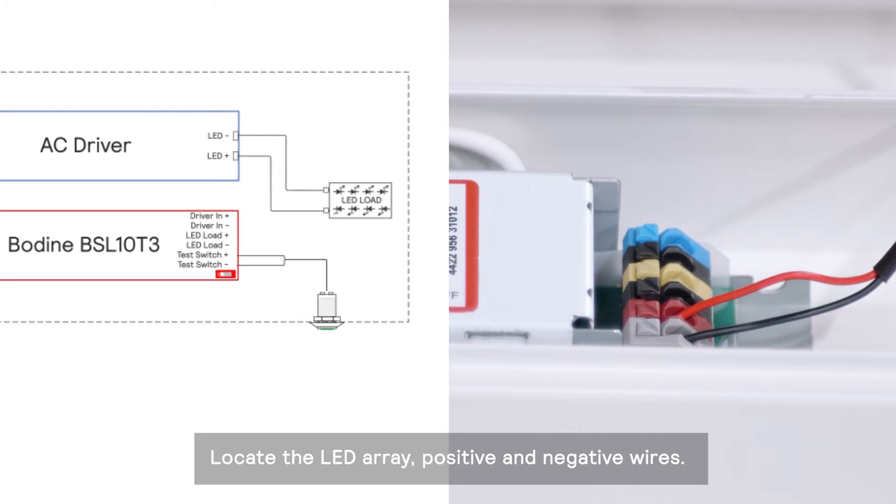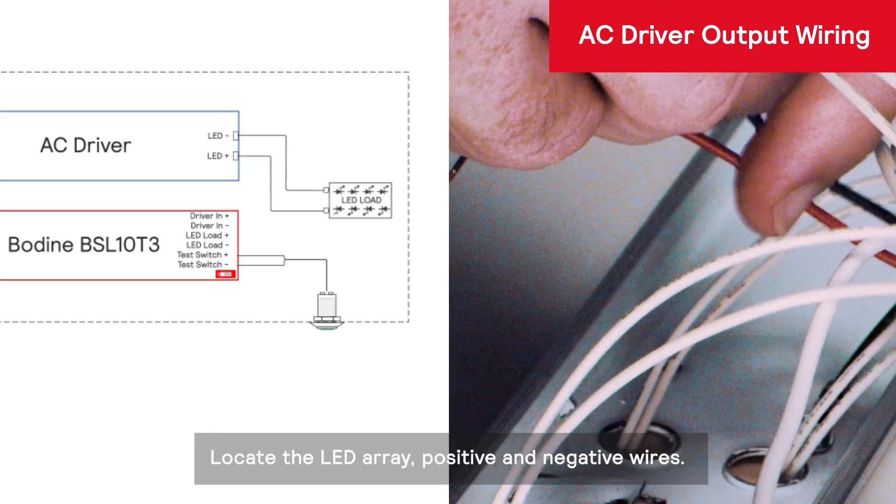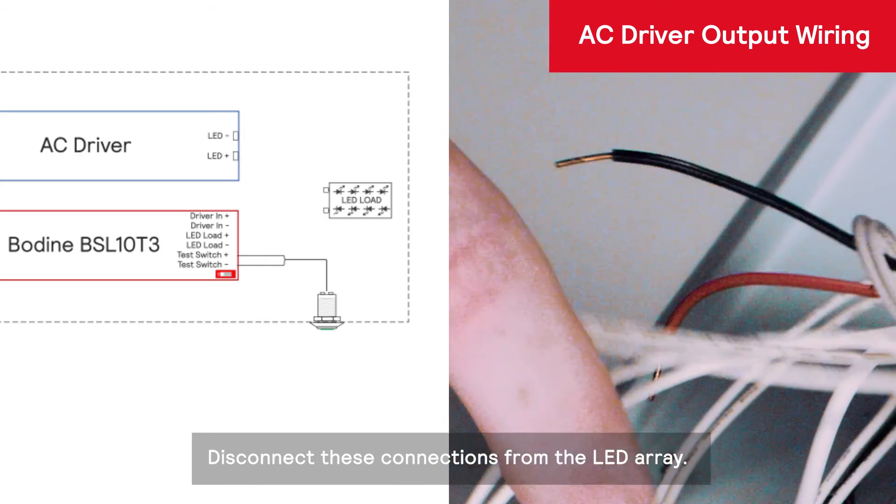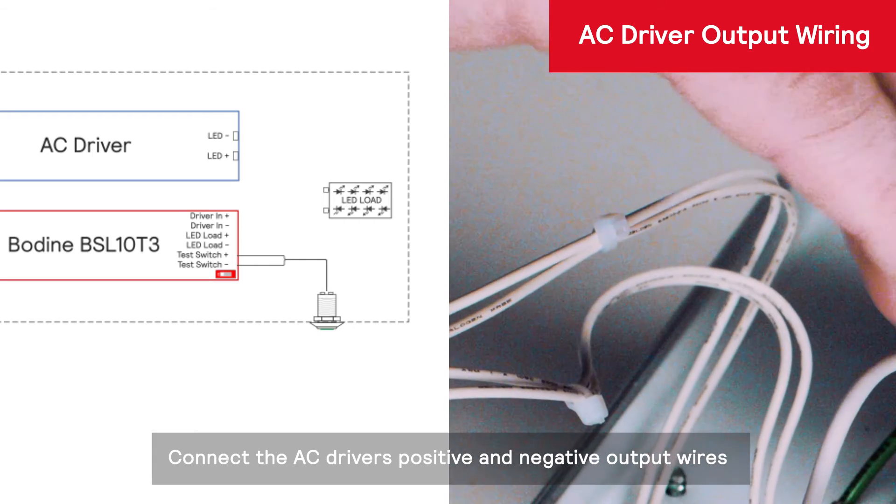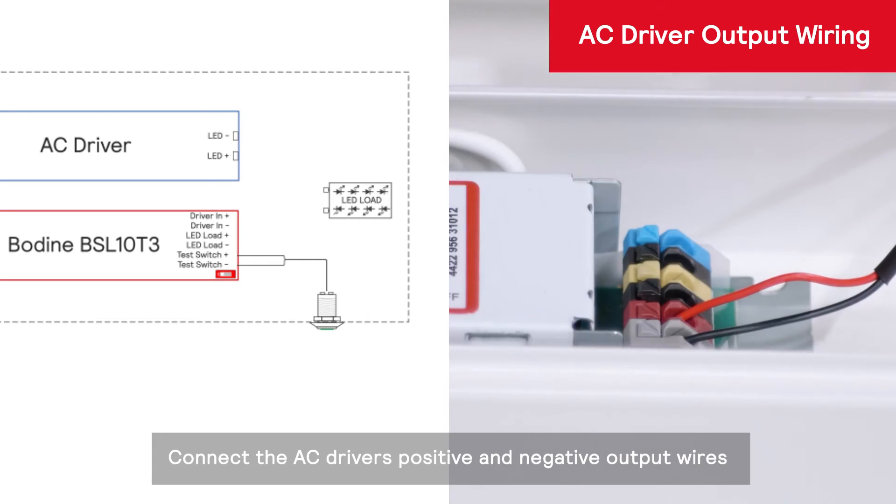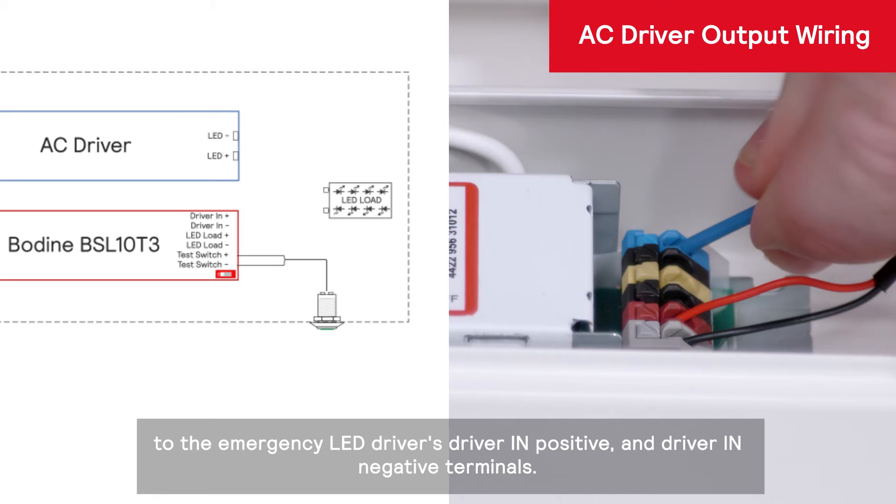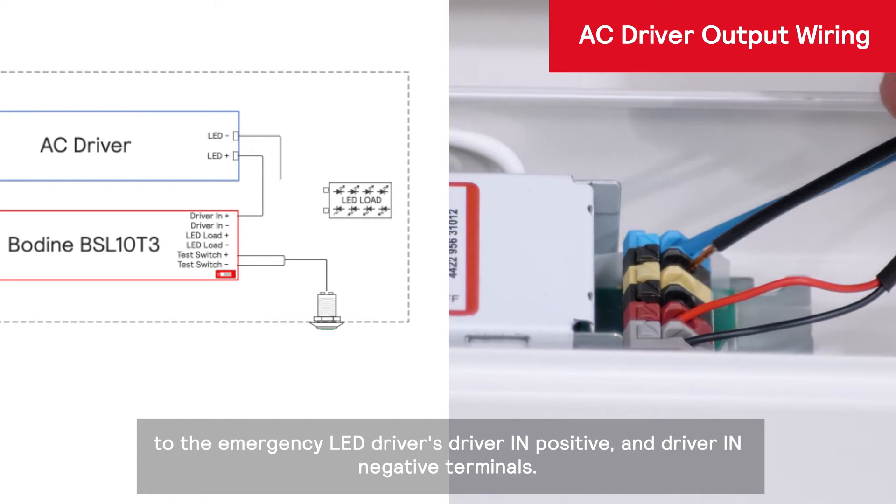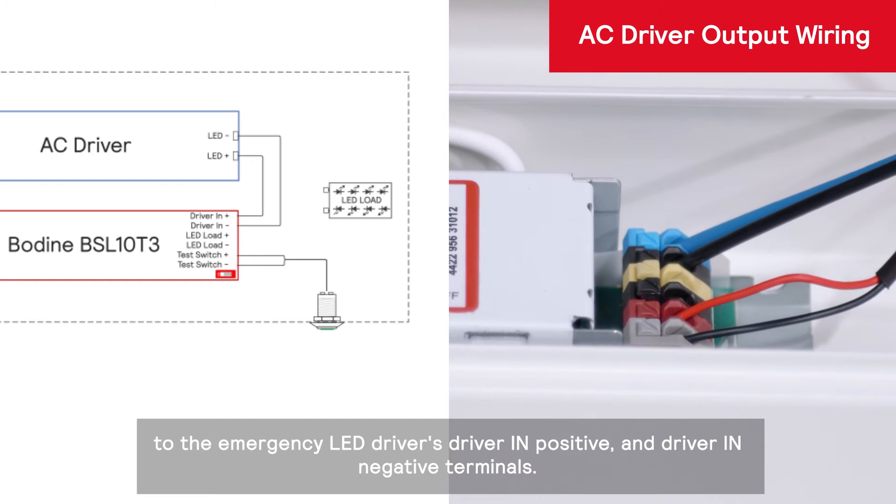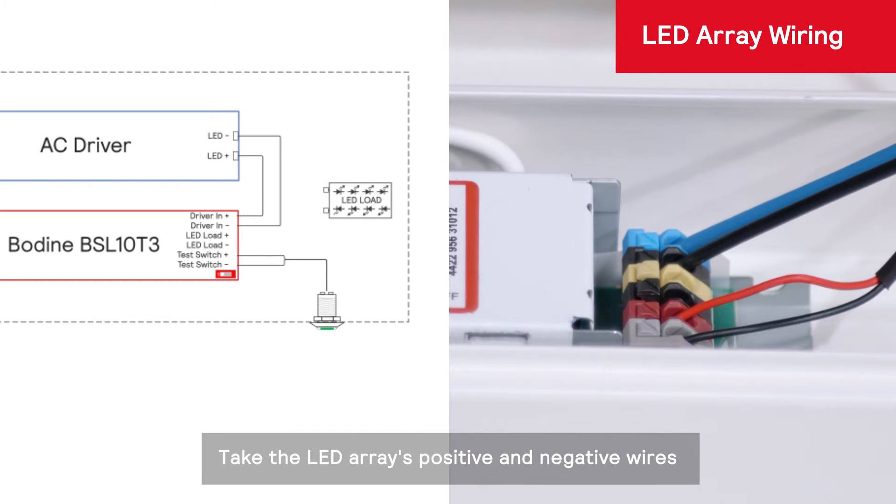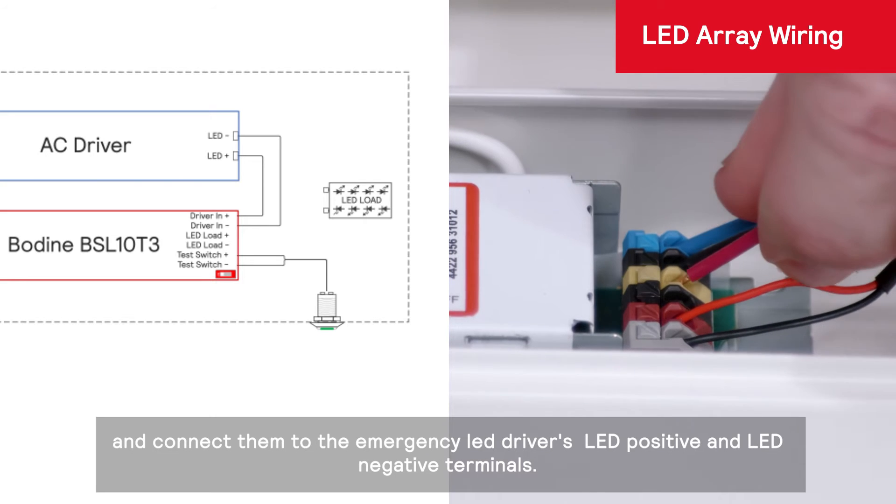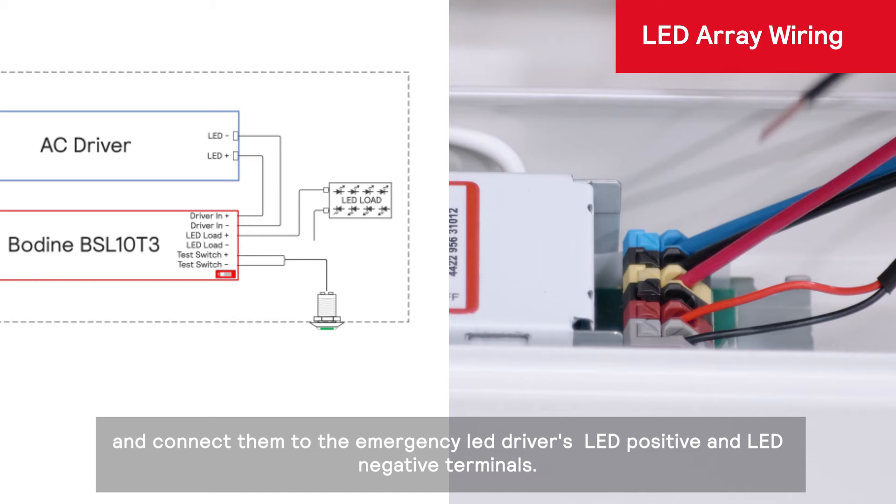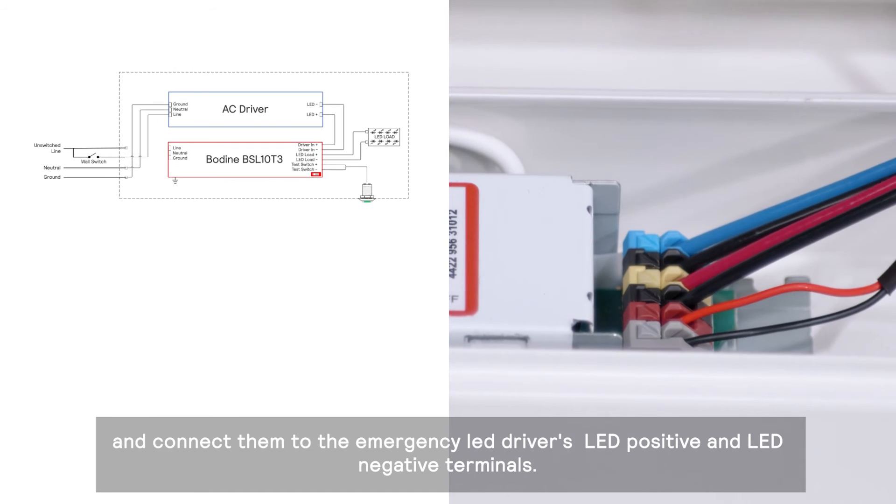Locate the LED array positive and negative wires. Disconnect these connections from the LED array. Connect the AC driver's positive and negative output wires to the emergency LED driver's driver in positive and driver in negative terminals. Take the LED array's positive and negative wires and connect them to the emergency LED driver's LED positive and LED negative terminals.